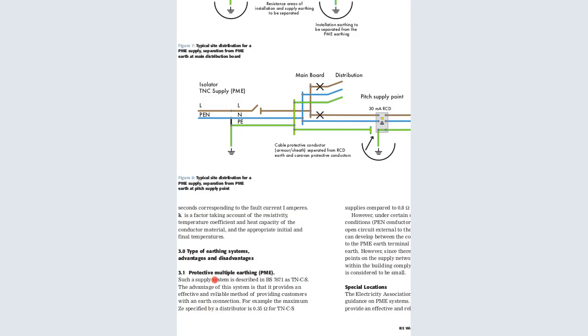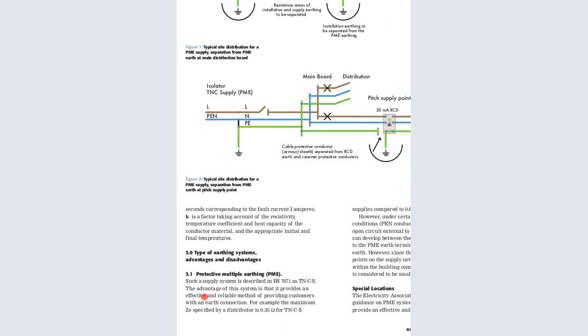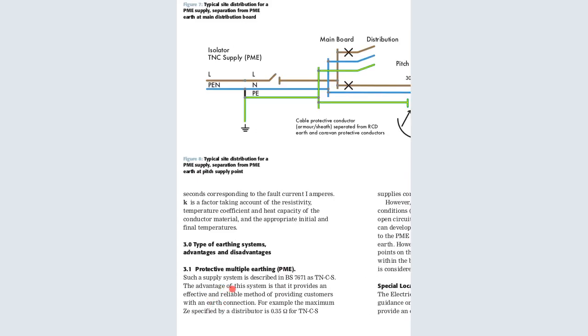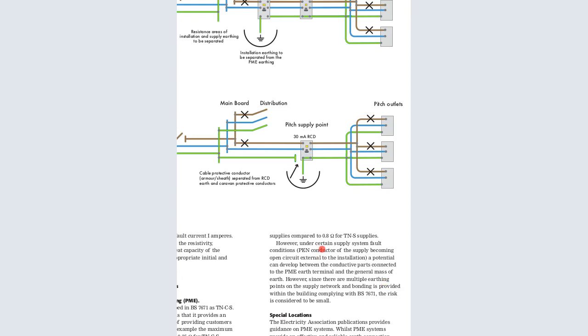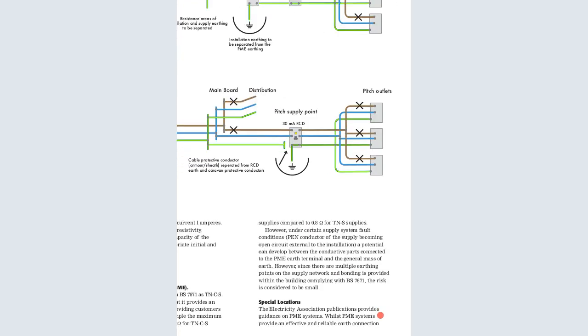Now, protective, these are known other types of earthing system. Protective multiple earthing, that is the PME. Such a supply system is described by the BS standard as the TNCS, and the advantage of this system is that it provides an effective and reliable method of providing consumers with the earth connection. For example, the maximum Ze, that is the resistance specified by the distributor, is 0.35 ohms for this system, compared to the 0.8 ohm TNS supply.